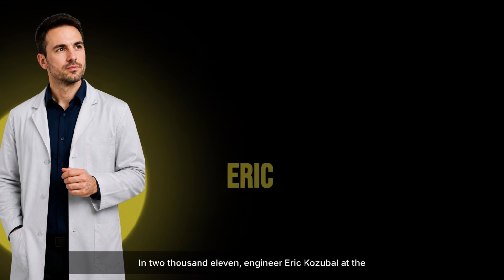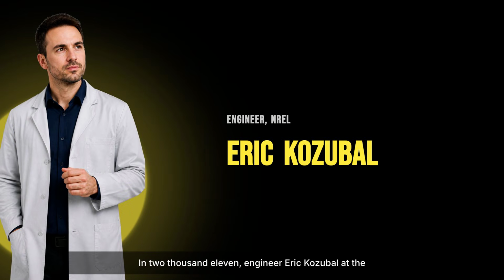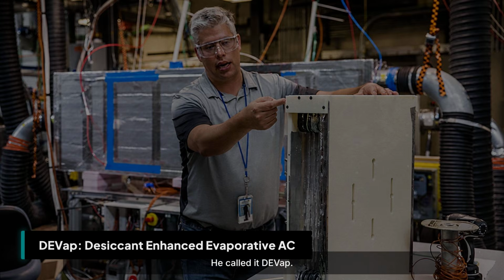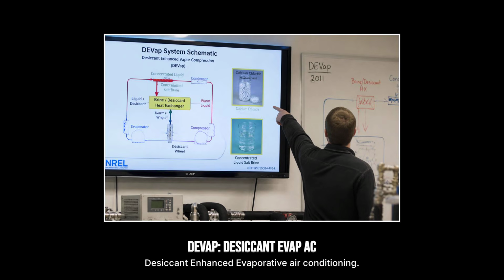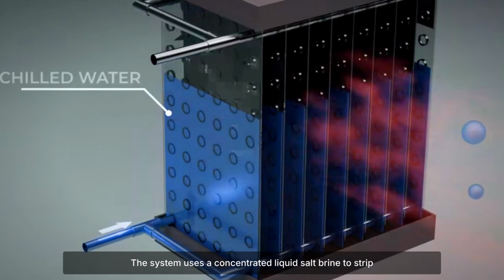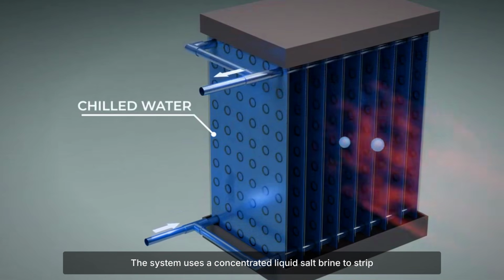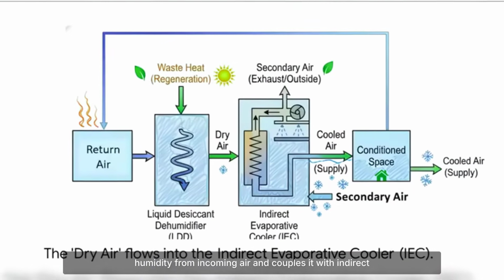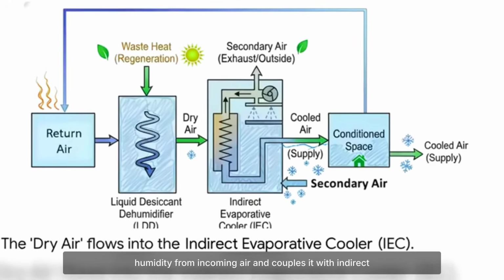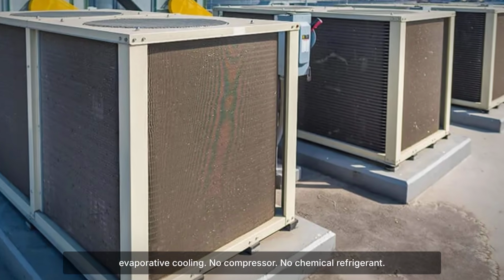In 2011, engineer Eric Kozubal at the National Renewable Energy Laboratory in Golden, Colorado, built something remarkable. He called it DEVAP, Desiccant Enhanced Evaporative Air Conditioning. The system uses a concentrated liquid salt brine to strip humidity from incoming air and couples it with indirect evaporative cooling. No compressor, no chemical refrigerant.